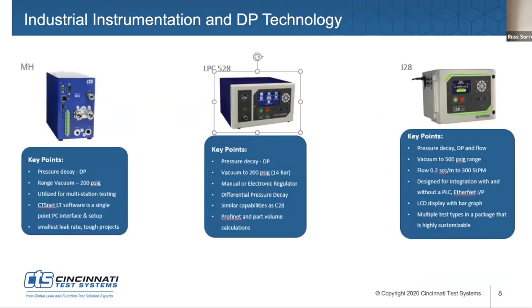Excellent. Let's talk about some of these industrial applications. Yeah, so these are 3 of the CTS instruments that support DP technology. Our latest MH instrument, it's a headless unit. It interfaces and is set up through a PC interface. The really nice thing about that instrument and the PC interface, you can actually see pressure curves very easily and start your test, stop your test through the PC.